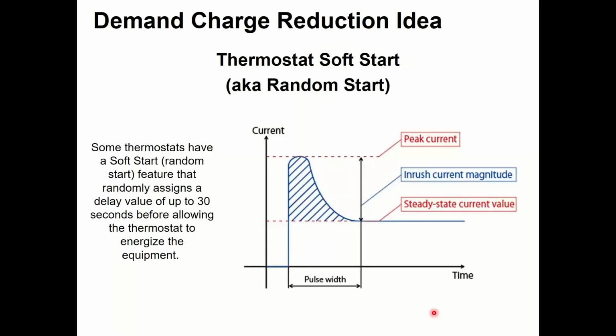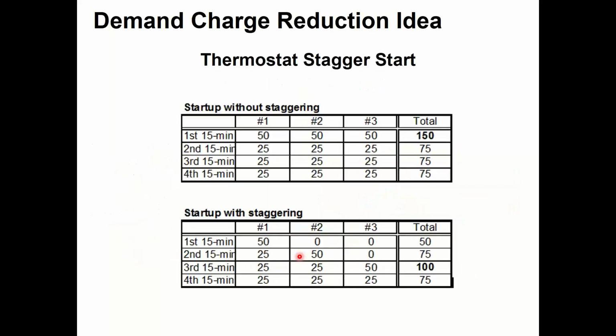Your thermostats can also help out with demand charge. Not every thermostat does this, but some do. Some of them will stagger the start of the equipment. So if the equipment's all supposed to come on at 7 a.m., it may start one unit at 6:45, another one at 7, another one at 7:15 to stagger the start. When I first turn a piece of equipment on, if it's an inductive load, so like a PSC style motor, when that motor or compressor kicks on, it has an inrush of current, and then a couple tenths of a second later that drops down. I'd like all those peaks to not happen at the same time. It'll lower my inrush current, and it'll make it less likely that that affects my peak demand.